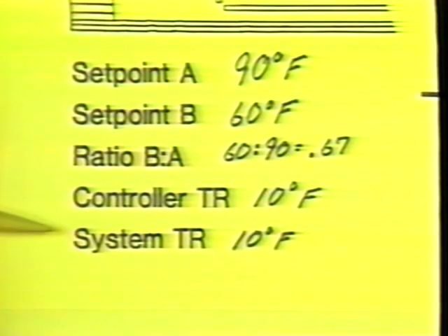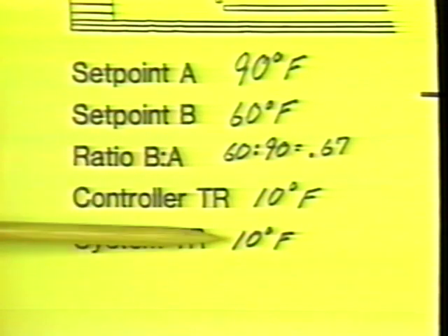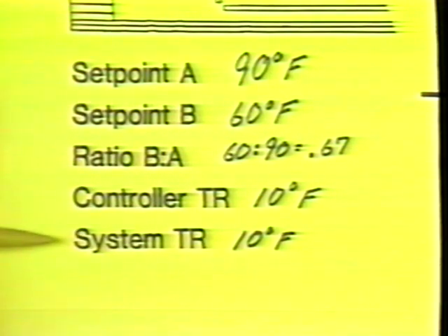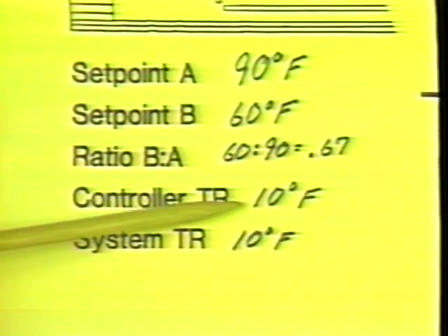System throttling range. System throttling range is not an actual setting on the controller. However, it's directly related to controller throttling range. Remember, whatever the controller throttling range, that change in variable will give us a 3-volt change in controller output signal. If the entire hot water system can respond to that 3-volt change, and in fact requires only a 3-volt change for full response, then the system throttling range and the controller throttling range are the same, as shown here. However, if the system responds to less than 3 volts or more than 3 volts, then the system throttling range will be less or greater than the controller throttling range.